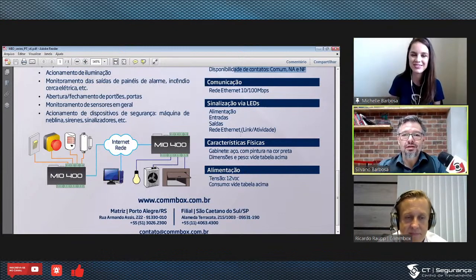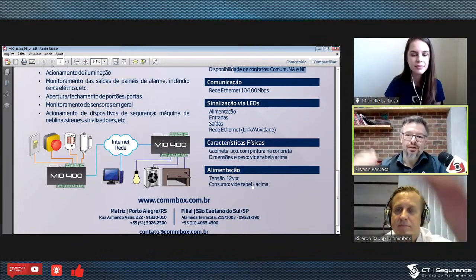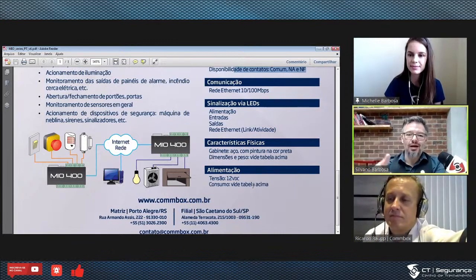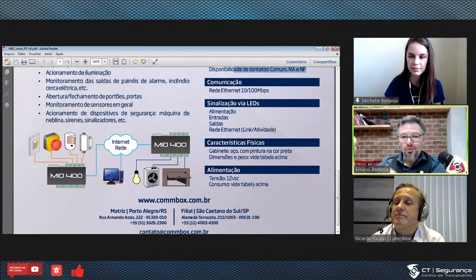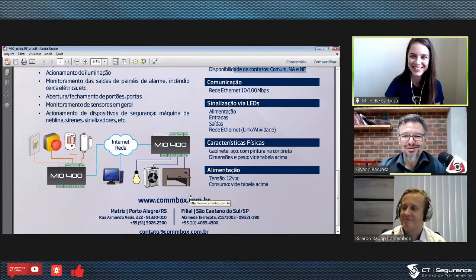Existem dois motivos principais para usar a contatora: primeiro, a questão da potência. Segundo, a contatora facilita multiplicar as entradas e saídas. Se tiver um quadro com oito terminações diferentes, em vez de juntar tudo num único borne, pego uma contatora com múltiplas saídas. E a vantagem é que se tiver algum problema na outra ponta — um curto elétrico, por exemplo — a contatora vai sofrer a carga, e a Multi-IO fica protegida. Eu já aprendi isso da melhor forma possível.